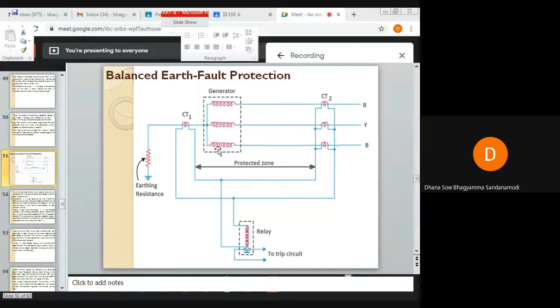So this protected zone is only for protection of this alternator winding against the earth faults, not for phase-to-phase faults. Under normal operating condition of this balanced earth fault protection scheme, the currents flow through the primaries of these CTs. Because of the current flow in the primaries, the EMF will be induced across the secondaries, and hence current will flow through the secondaries of all these three CTs. Since they are connected in parallel, the resultant current coming out of the pilot wire will be equal and opposite to the secondary current flowing through this pilot wire.